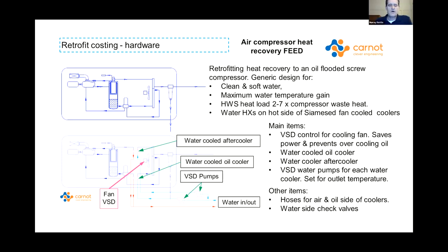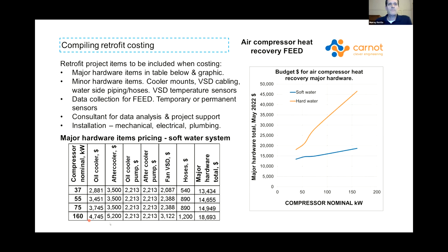I'll jump through quickly. So what'll be of benefit for a lot of people? This is budget pricing for different size machines for the different items that you need to retrofit. The slide before it provides you some information on what heat flow rates and water flow rates you need for different size coolers. As I said, these are all flooded machines. This data is plotted off here. So it gives you an idea of what the cost for these major hardware items are, but you've got to add in your VSD cabling, temperature sensors, an allowance for people like me to help you design everything and put it in properly and commission it all.